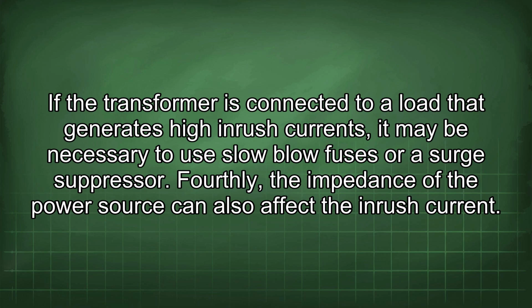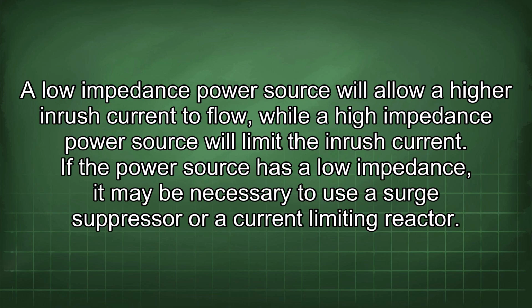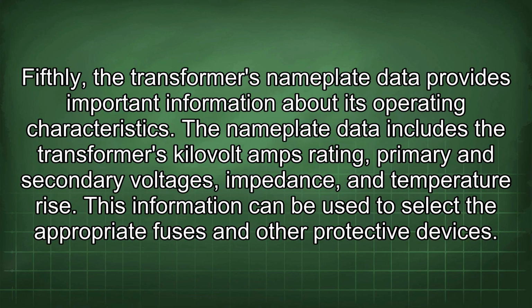Fourthly, impedance of the power source can also affect the inrush current. A low impedance power source will allow a higher inrush current to flow, while a high impedance power source will limit the inrush current. If the power source has a low impedance, it may be necessary to use a surge suppressor or a current limiting reactor. Fifthly, the transformer's nameplate data provides important information about its operating characteristics. The nameplate data includes the transformer's kilovolt-amps rating, primary and secondary voltages, impedance, and temperature rise. This information can be used to select the appropriate fuses and other protective devices.